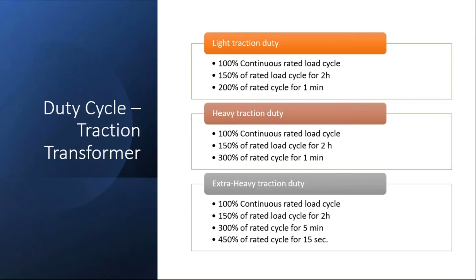Most of the transformers which we see, design, and manufacture are on extra heavy duty constraints. Actually, it is a simulation of trains going across the various train stations and how the transformer loading is affected. It's assumed that in these peak hours, it will have a continuous load of 150% for 2 hours. Beyond 150%, when there are multiple trains crossing the station which this transformer is hooked up to, the load will go up to 300% or 450%. That's how it is classically defined, and they equate it to the percent run for those 2 hours. For instance, for extra heavy traction duty, it's 160.3% of the nameplate rating.